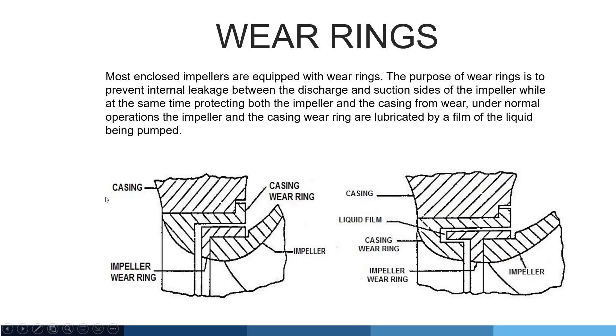Wear rings. Most enclosed impellers are equipped with wear rings. The purpose of the wear rings is to prevent internal leakage between the discharge and suction sides of the impeller while at the same time protecting both the impeller and the casing from wear. Under normal operation, the impeller and casing wear rings are lubricated by a film of the liquid being pumped.